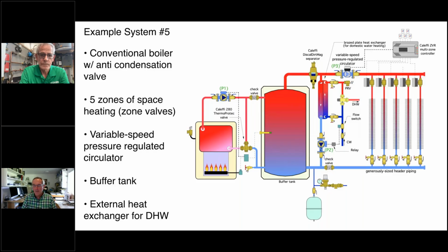This actually gives you the advantage of the heat exchanger being external to the tank. You see there's a couple valves here on the domestic side. These are just purge valves. We can close the two inline ball valves and we could actually pump a mild acid solution through that side of the heat exchanger. If we have any scaling, we can reduce that.